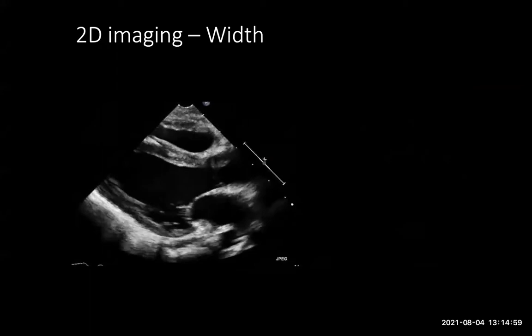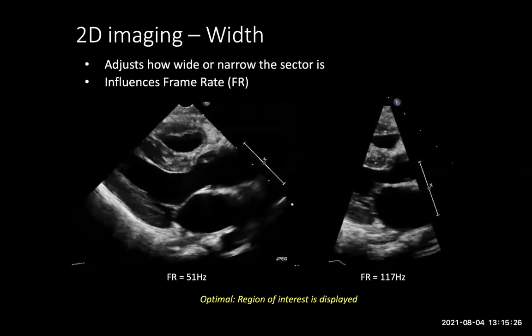Next is width. It changes how wide or narrow your sector is. It also influences frame rate because it changes the number of scan lines that are needed to create the image. This image has the max width of the sector with the frame rate of around 51 Hertz. But if we wanted to focus on the mitral valve, we can narrow the sector to cover just the mitral valve. And here we've got the frame rate of 117. So the optimal width is dependent on what the region of interest is.